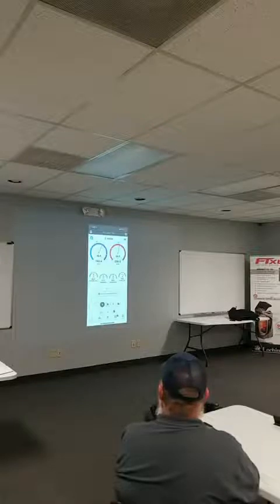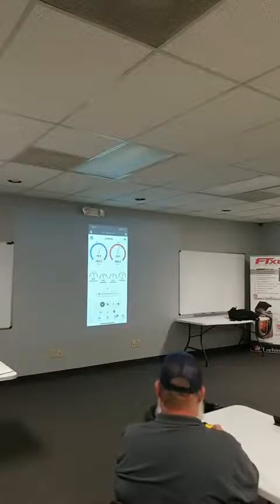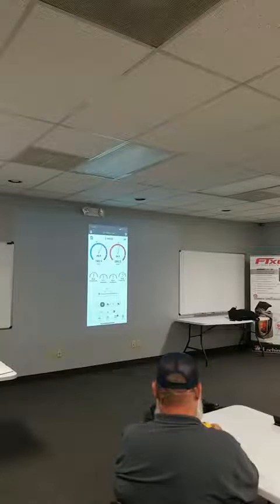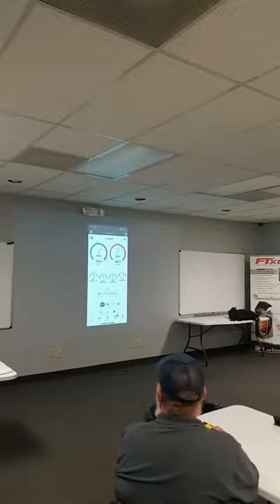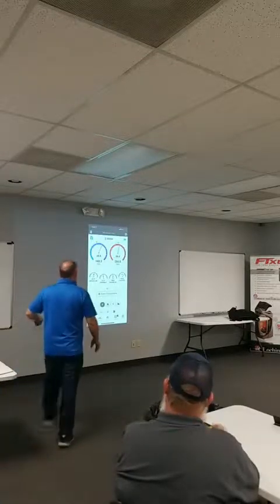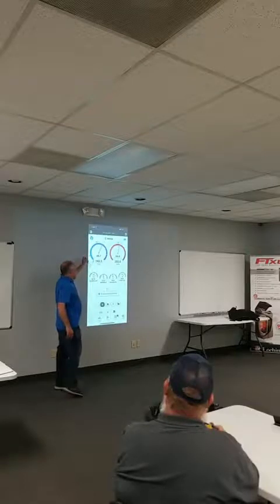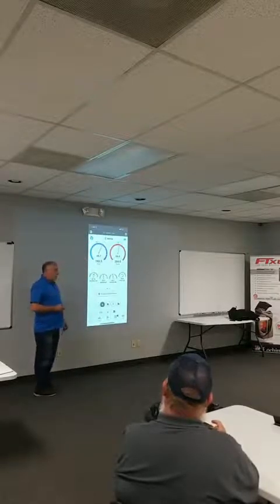Because it's calculating what the liquid line temperature should be based on the outdoor air conditions, but who knows, we got a little bit of an issue with the short circulation of the air. It could be garbage in, garbage out on that machine. Now, I don't have this on a benchmark anymore either. I cleared the benchmark out, and it's telling us, hey, it's in the range. Now, I know the suction pressure is high here, right? But that's not really an issue.